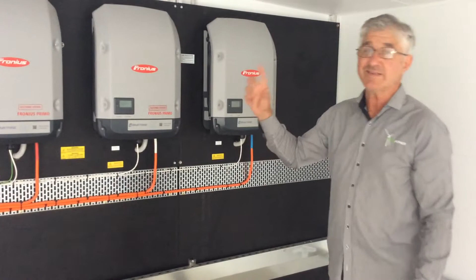So in a couple of years the farmer here will need about 44 kVA. So basically all we need to do is replicate what we have on this wall and put it on another wall and join the two systems up via communications cable, and we'll go from 22.5 kVA to 44 kVA, which basically has augmented his grid. We've lifted his grid from 12 kVA to an eventual 44 kVA.